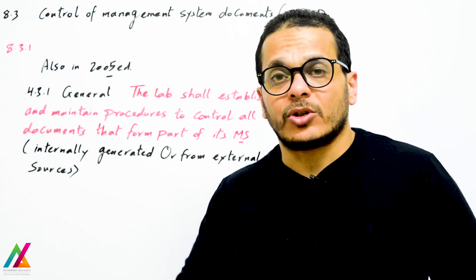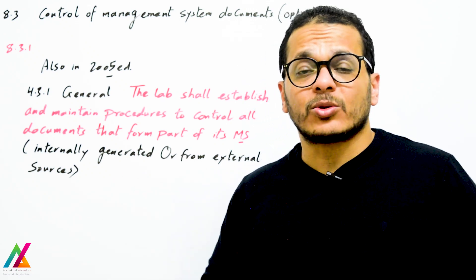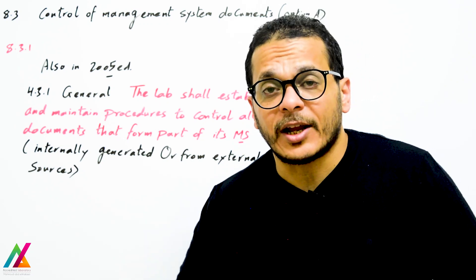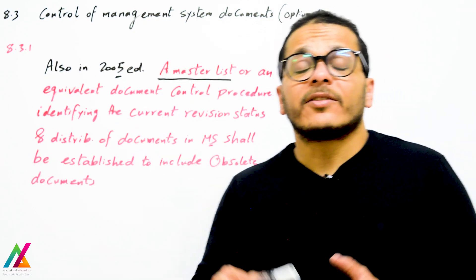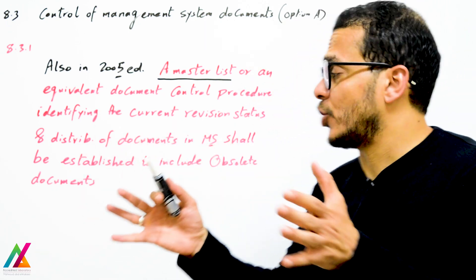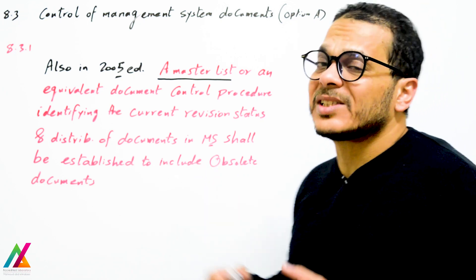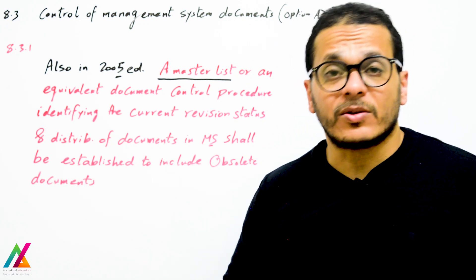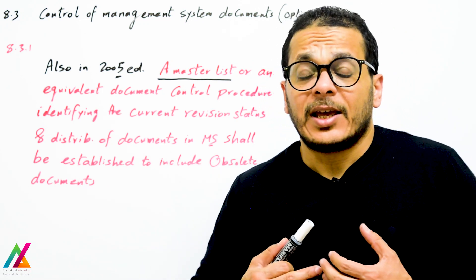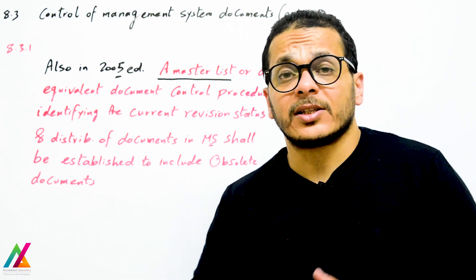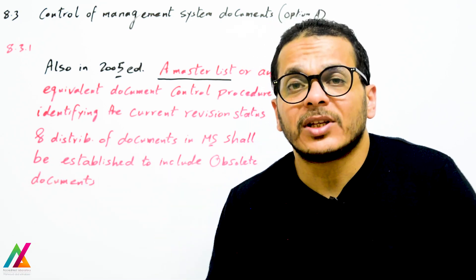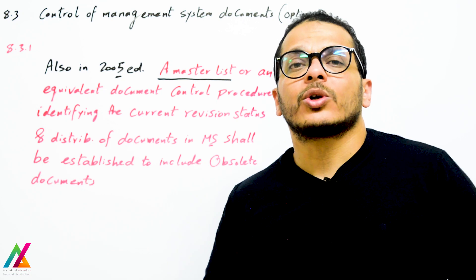If your lab was already accredited according to the 2005 edition, you have this procedure and can keep it. If you don't want to keep it or prepare a new one, that's no problem. Also in the 2005 edition, a master list or equivalent document control procedure identifying current revision status and distribution shall be established. Master list was required in 2005 but is not mentioned in 2017, however it remains very useful to organize all documents.